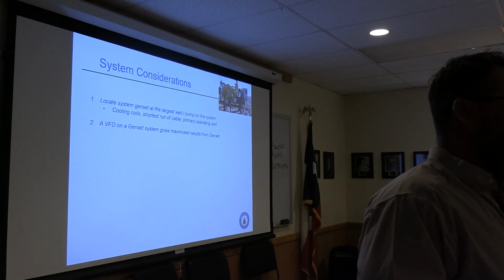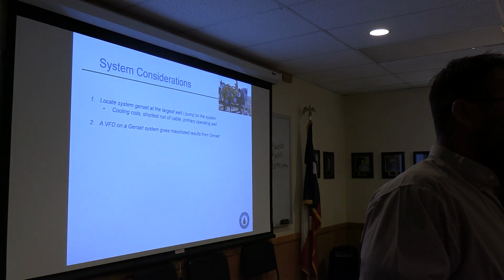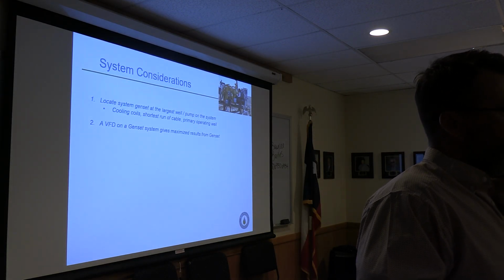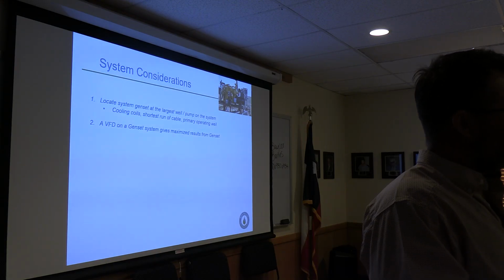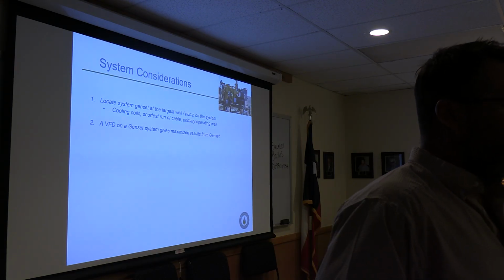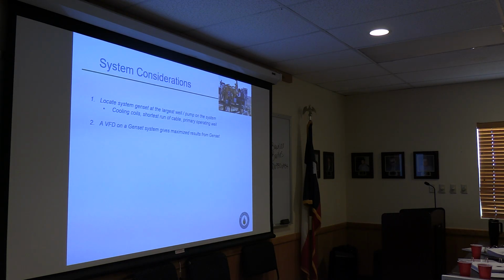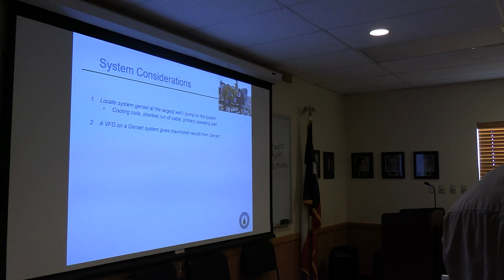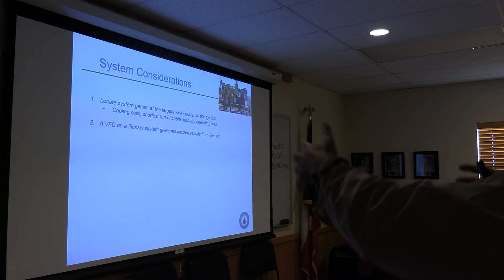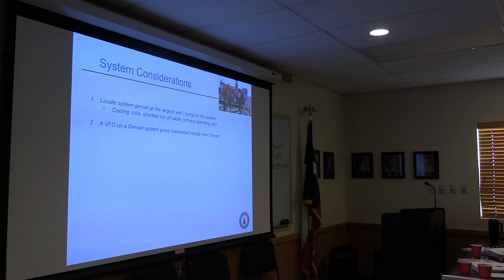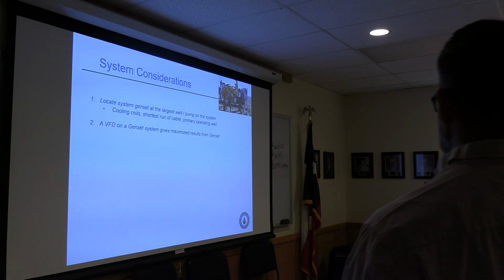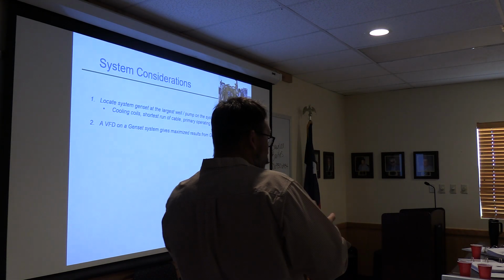I was testing a lot of submersibles for a while in that 3 to 30 horse range, and the starters were always buzzing, just buzzing. They were off phase. Okay, so I think I measured some that power factors were in the 70s. That's just kind of bad power. You cure that with the gen set. Also the VFD at those locations allows you to receive this bad power.